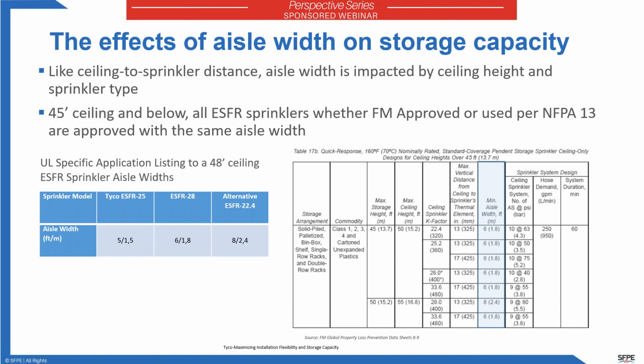Typically, we look at a 4-foot aisle for 45-foot ceiling and below. However, once you get above 45 feet, all bets are off with regards to the aisle width. So for instance, I mentioned that there are different sprinklers that have a UL specific application listing to 48-foot ceiling. And all 3 sprinklers have different aisle width approvals. So for instance, the ESFR 25 that Tyco manufactures, JCI, our 48-foot listing is with a 5-foot aisle.